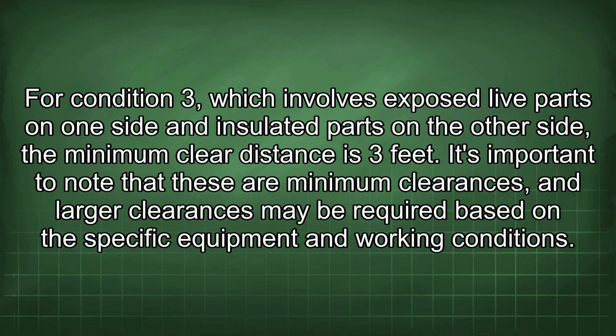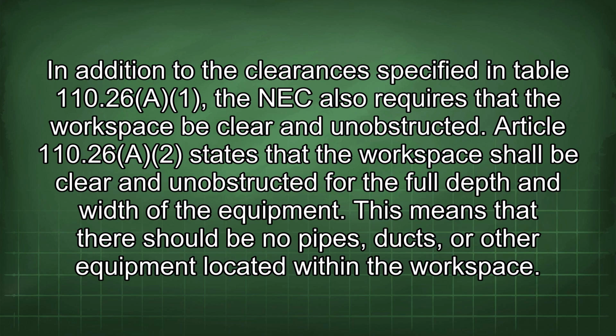and working conditions. In addition to the clearances specified in Table 110.26, the NEC also requires that the workspace be clear and unobstructed. Article 110.26 states that the workspace shall be clear and unobstructed for the full depth and width of the equipment. This means that there should be no pipes, ducts, or other equipment located within the workspace.